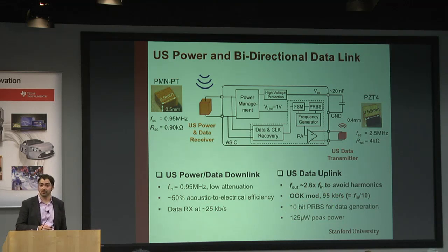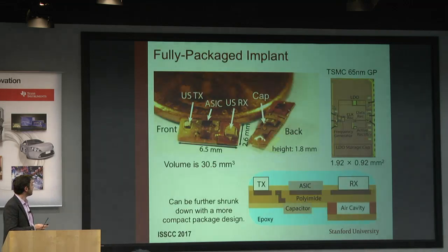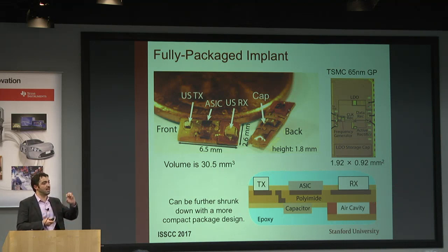This is what the packaged implants look like for this communication system. We're using polyimide substrates, and we cover it with an epoxy. We're moving towards medical grade epoxies. We're sending some of these devices to the FDA. They're running their independent tests to see if what we're saying actually makes sense. They're doing thermal cycling, looking at long-term stability, and a lot of other questions are being answered.